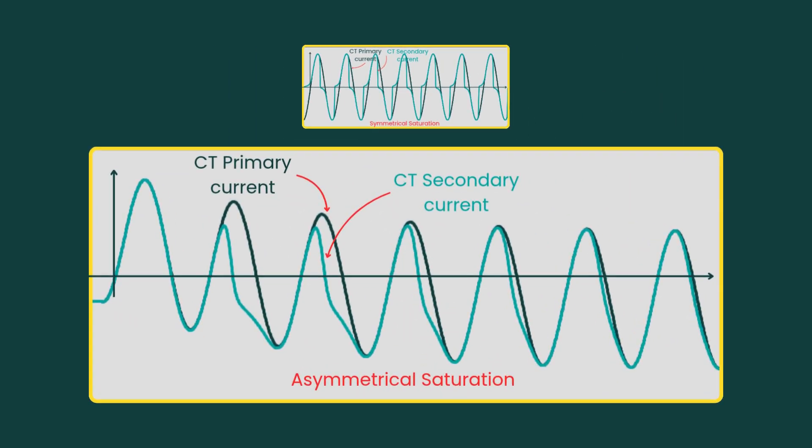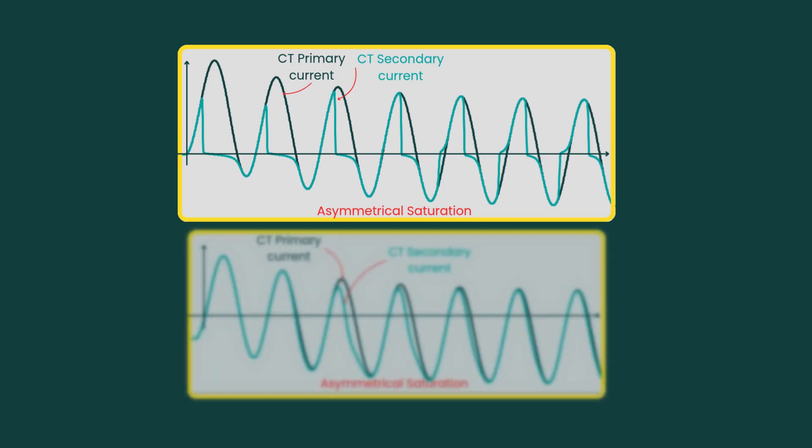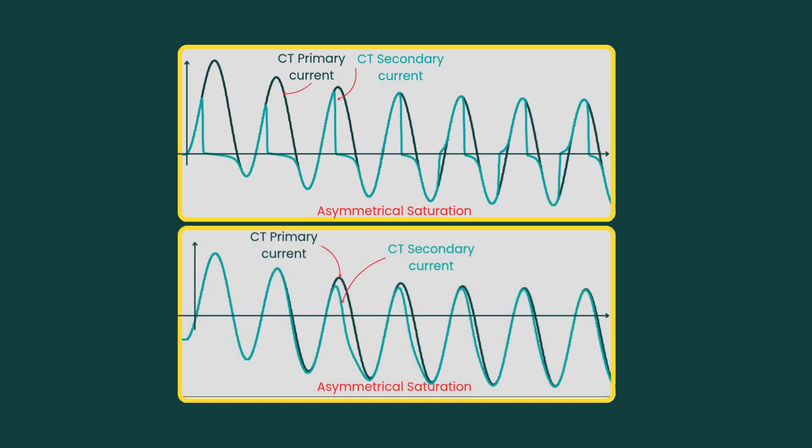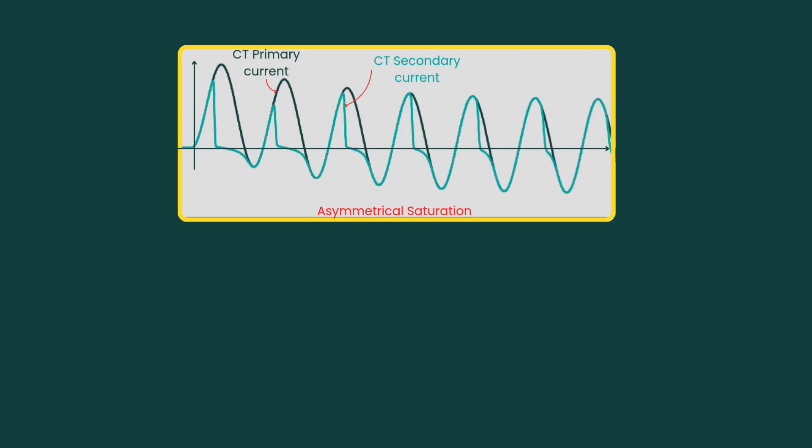Asymmetrical saturation is different. It happens because of DC offset in the current. Depending on the fault current, DC offset, and the system's X by R ratio, the CT might saturate immediately or after a few cycles, and saturate in one direction only or in both directions.